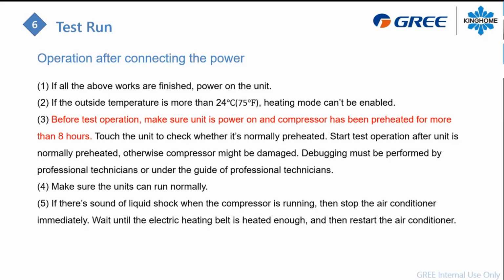Make sure everything runs normally. When you make some installs, you will hear the noise. Make sure you don't hear any knocking noise when starting the compressor or stuff like that. So for example, if it's cold and you try to start it and maybe you can hear the sound of the liquid sucking into the compressor, stop it immediately. So try to avoid damaging the compressor from day one just because you're in a hurry. Just wait till the compressor is warm enough to run it properly. Other thing, when it's minus 15 degrees Celsius, the cooling mode is disabled as well. So you will not be able to use the cooling mode at minus 15 degrees.